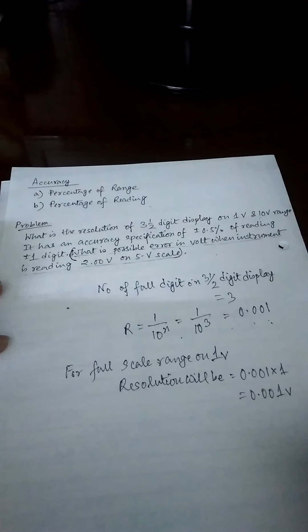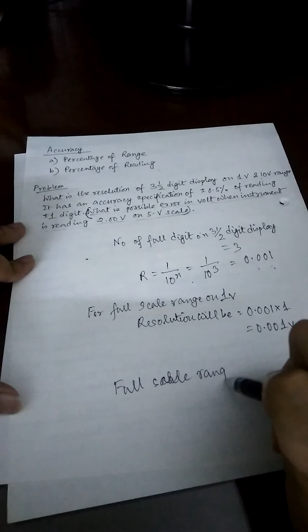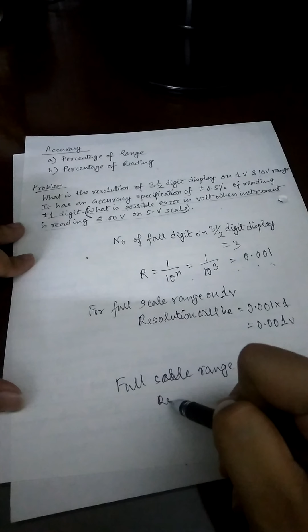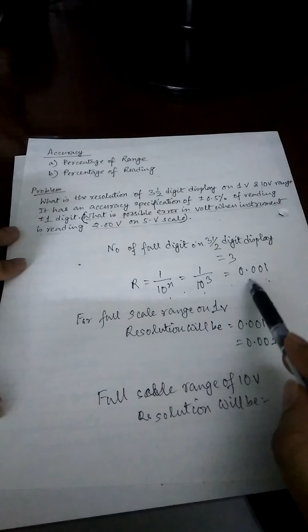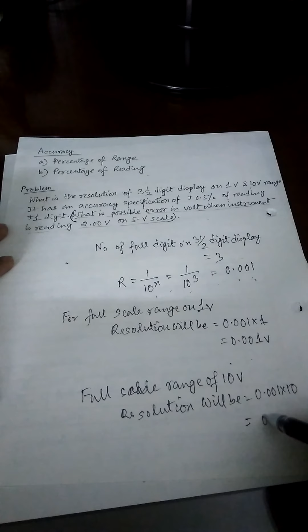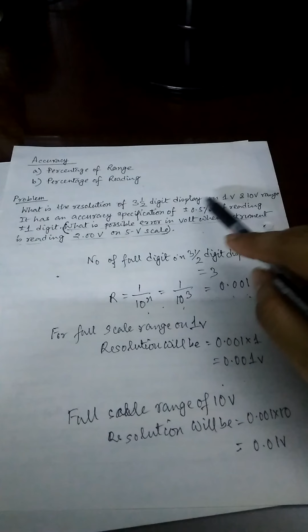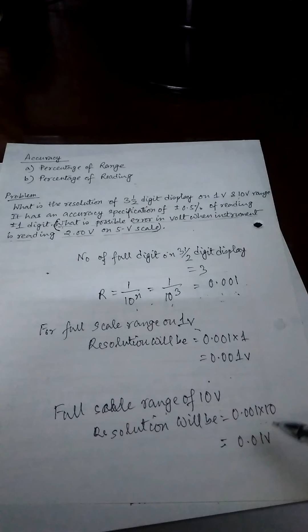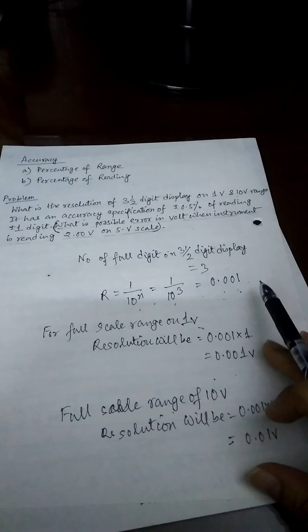When we consider the full scale range of 10 volts, what happens? The resolution for the 3.5 digit display is 0.001. For the full scale range of 10 volts, the resolution will obviously be 0.001 into 10, that means 0.01 volt. So this is the actual outcome when we consider the full scale values in a particular meter. For a 3.5 digit display, the common resolution is 0.001. For the full scale range of 1 volt, the resolution is this, but for 10 volts it will be 0.001 into 10, that means 0.01 volt. By this we can do different problems.